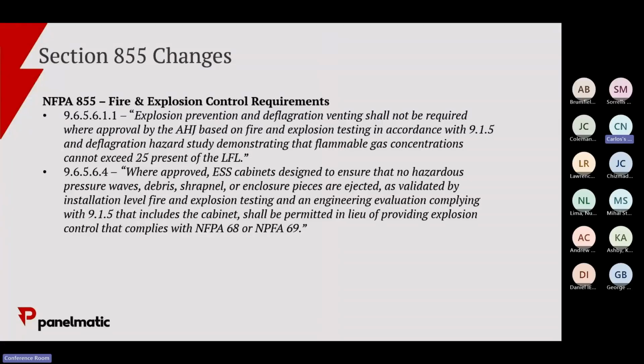So now it's, okay, we need to vent that gas, and if we can pick up the hydrogen as it starts emitting from the battery prior to it going into thermal runaway, you can try to prevent the thermal runaway event from even occurring. They're trying to keep that lower flammable limit and detect it earlier, because the thought is if you can catch it before it goes into thermal runaway, you might be able to stop it. This is all around managing the enclosure and things. I'll say the technology around the power electronics doing this is also rapidly catching up, so I think you'll start to see that play into this as well.